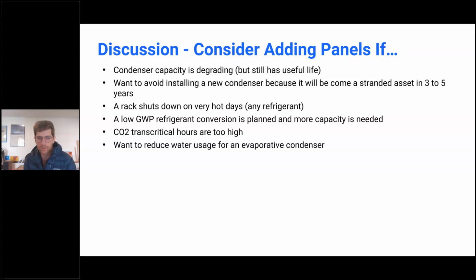They're not leaking, for example, and we can add capacity. So instead of replacing a condenser, we can add an array of panels. It's going to cost less, and it will have this efficiency benefit over the lifetime. You have, for example, issues where refrigeration or cooling systems are underperforming. They're derating because it's hot outside. You have a refrigerant conversion and you've lost capacity. So these are scenarios where you might want to put panels in.